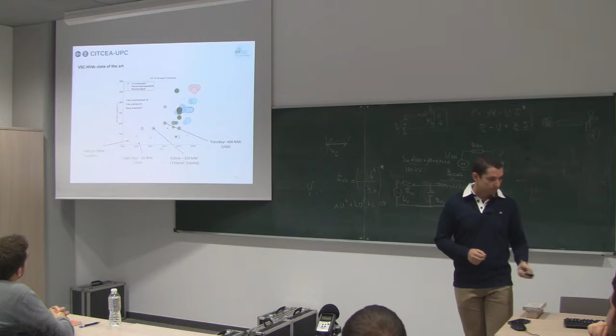I had a question that is not strictly related to the converters. Is there a rated power for the HVDC lines? I mean, if I'm fixing the voltage, is there a rating power... like for AC I can have 400 kilovolts, and I know that the natural active power I can transmit over long distances is 650 megawatts. Is there something like that? Because what's limiting is that afterwards you need series capacitors to compensate and extend the distance. So is there a rated power, or...?